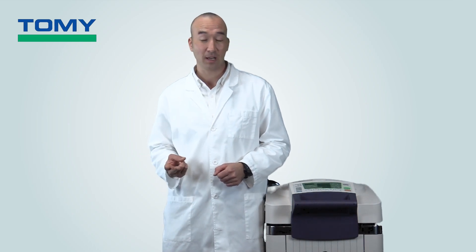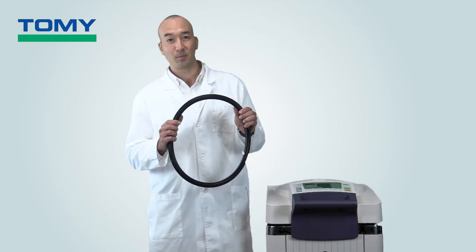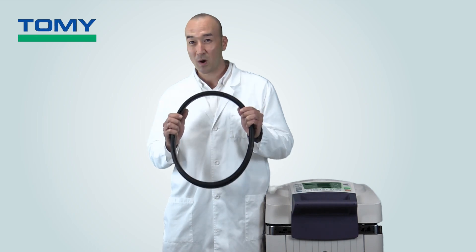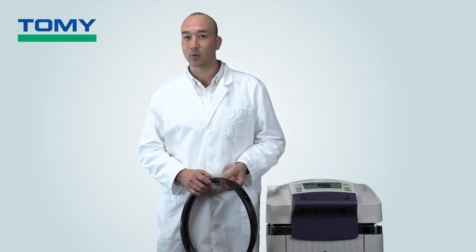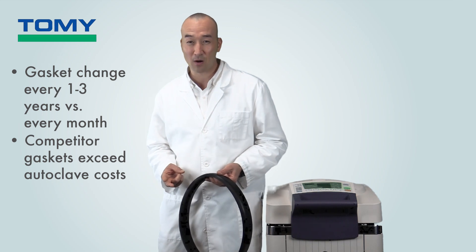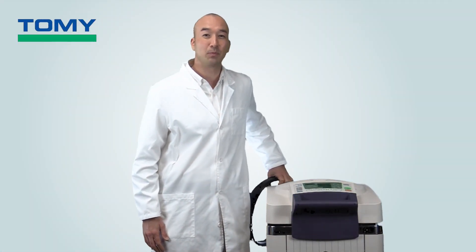Another important but often forgotten item is the lid gasket — always consider the type of lid gasket, how often it requires changing, and how much it's going to cost. This sturdy lid gasket from TOMY autoclaves lasts 1,000 operating hours, meaning it needs to be changed up to once every three years. Other manufacturers' lid gaskets require changes almost every month at several hundred dollars apiece, which can add up to more than the price of your autoclave in just a few years.